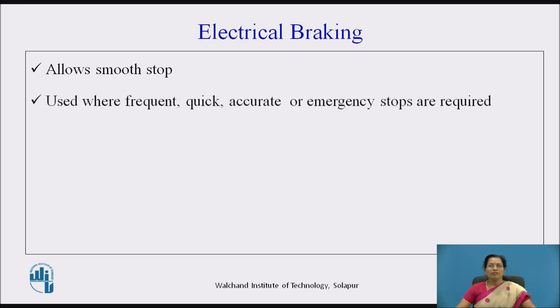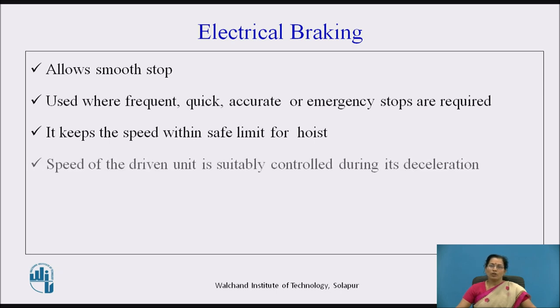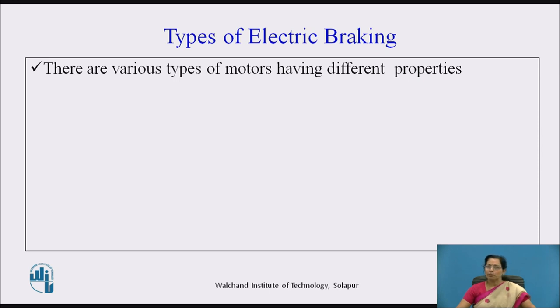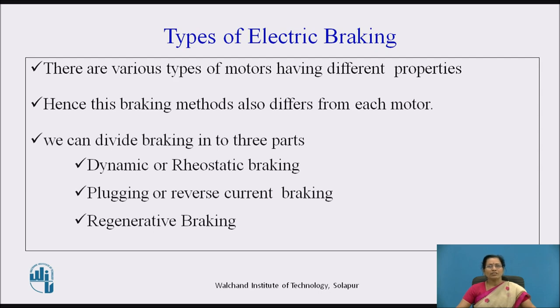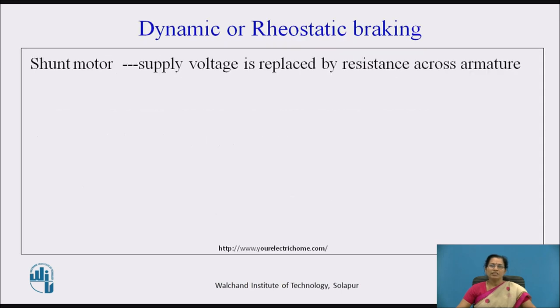Electrical braking is used where frequent, quick, accurate, and emergency stops are required. It keeps the speed within a safe limit for a hoist. Speed of the driven unit is suitably controlled during its deceleration. There are various types of motors having different properties, hence this braking method also differs for each motor. We can divide braking into 3 parts: dynamic or rheostatic braking, plugging or reverse current braking, and regenerative braking.